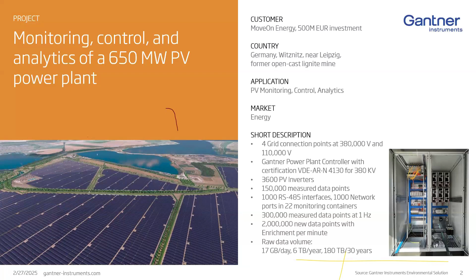A key part of the whole system is always a power plant controller. When you want to control the system, you have to absorb signals from the grid, from the operator, maybe from the O&M companies. You also have to be able to evolve over the lifetime what your power plant can do. You have to deal with voltage and frequency controls within seconds to adapt, but also be able to run hybrid power plants. So we do PV plus wind, PV plus batteries, and now also PV combined with electrolyzers.